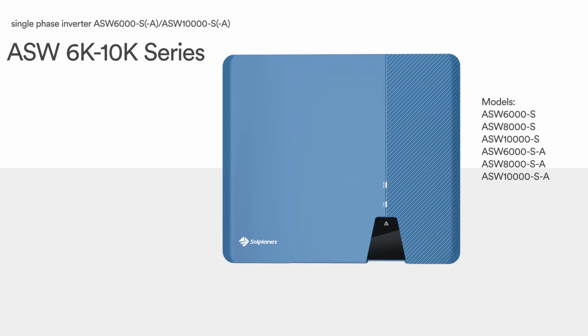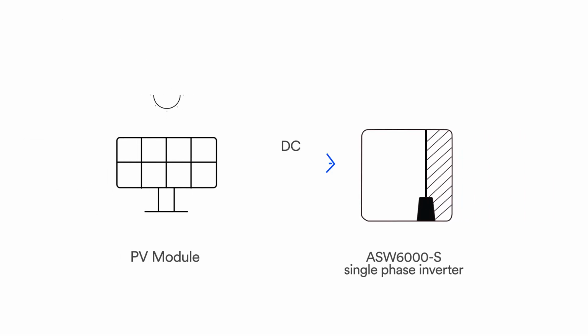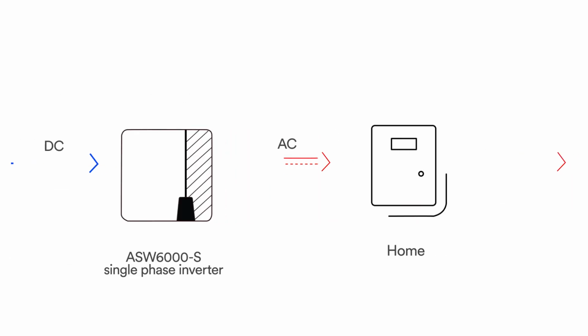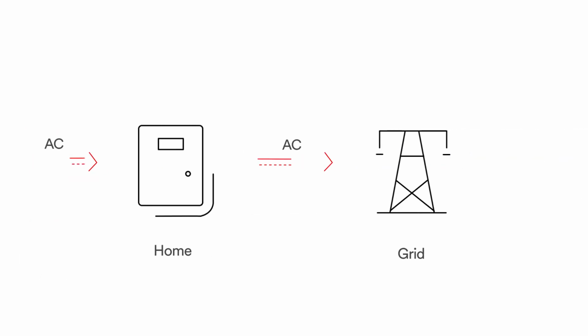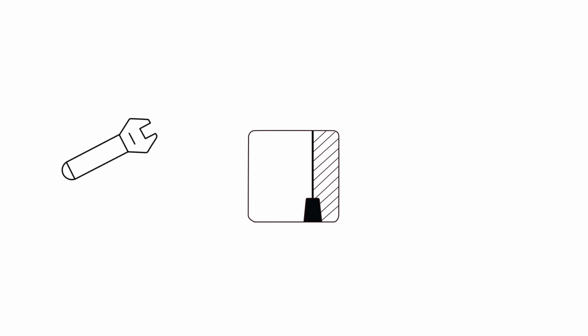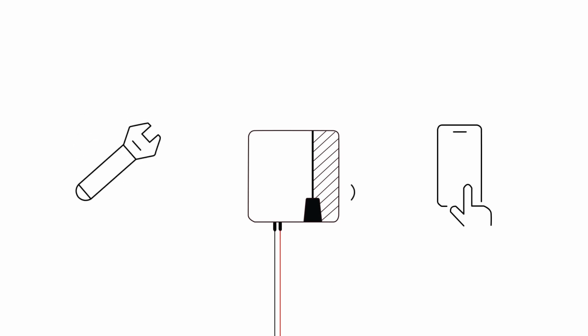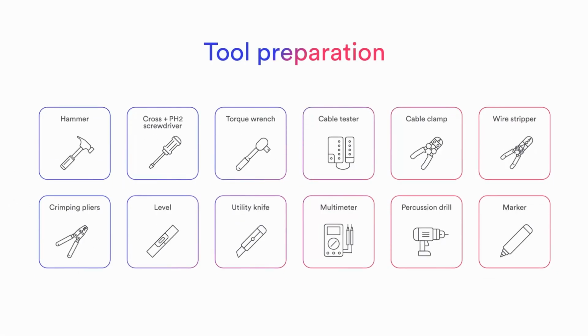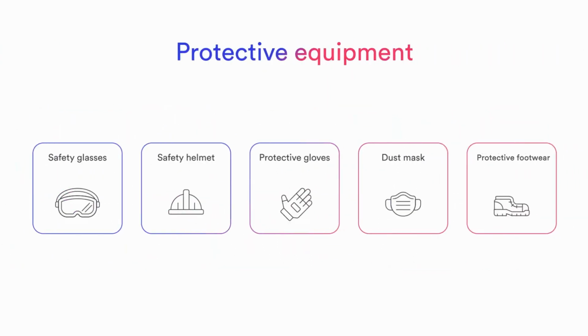Solplanet Inverter is a single-phase transformerless string inverter with 3 independent MPPTs. It converts the direct current, DC, generated by the photovoltaic PV module into a single-phase alternating current, AC, and feeds it into the utility grid. This video illustrates how to mount, install, and commission Solplanet Single-Phase Inverter. Solplanet inverters are quick and easy to install, only requiring a standard set of tools.